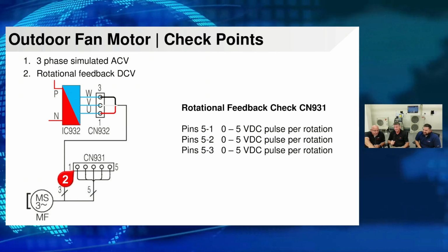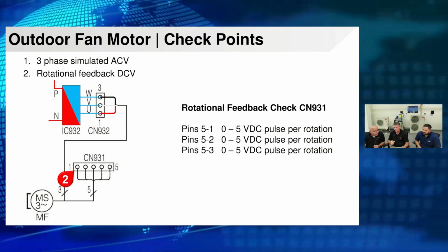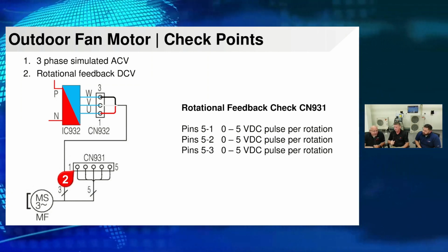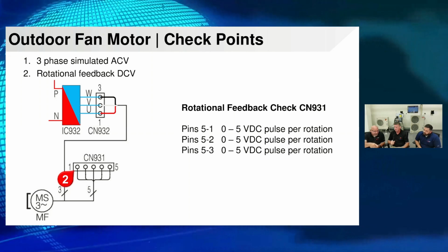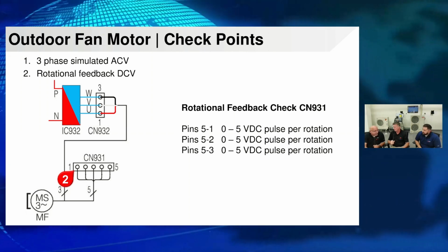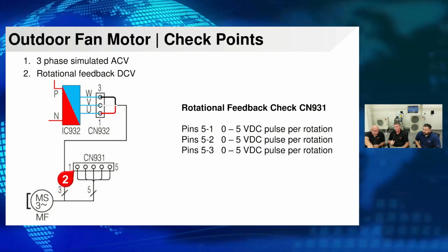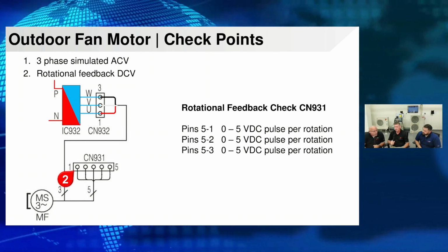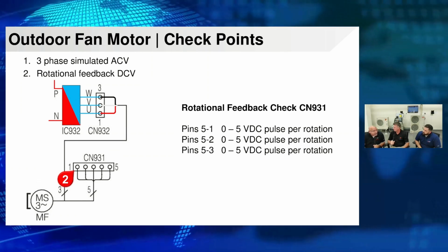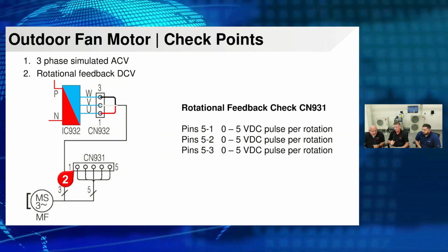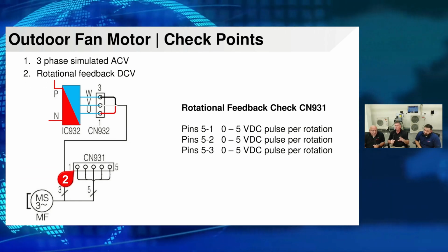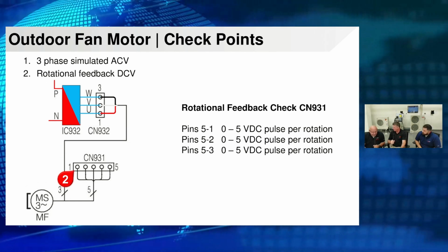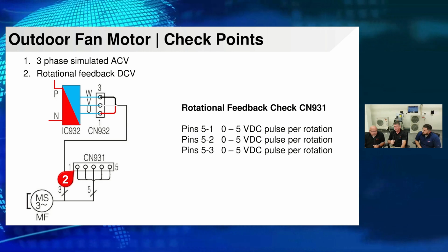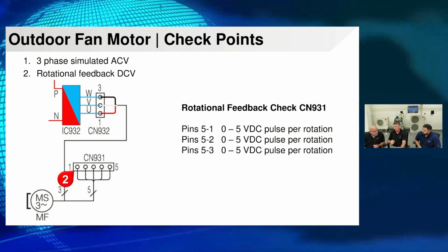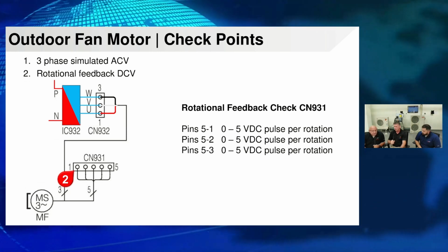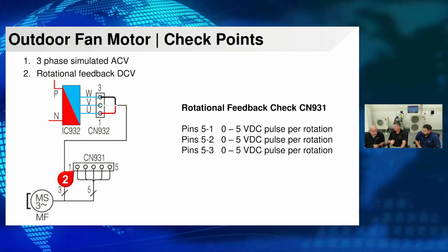Now, CN931 is your rotational feedback. So when that motor is rotating, it's sending a signal, in this case 5 volts DC, back through that plug into the board, and that's how the board knows that that motor is rotating. And all that is in the service manual. So we're just checking three-phase power, making sure that we have consistent three-phase power coming into the motor, and then we're just checking for that 0 to 5 volt DC across our pin terminals. That's it. Simple.